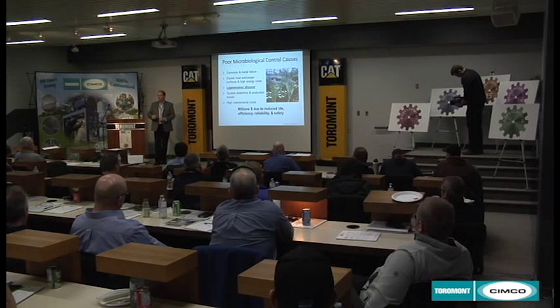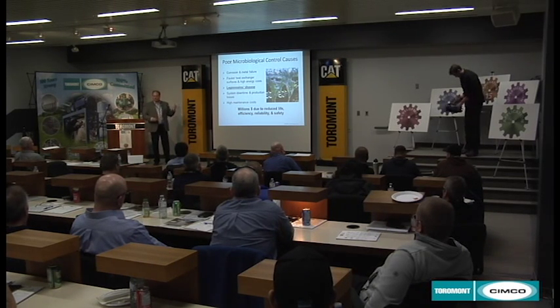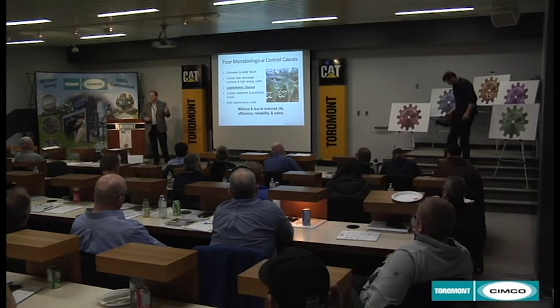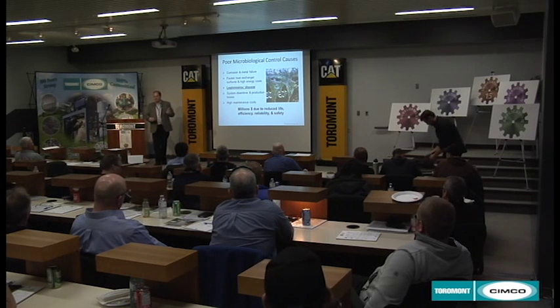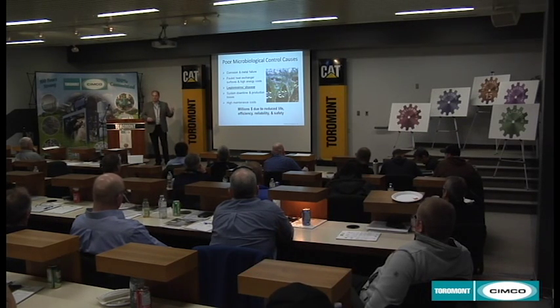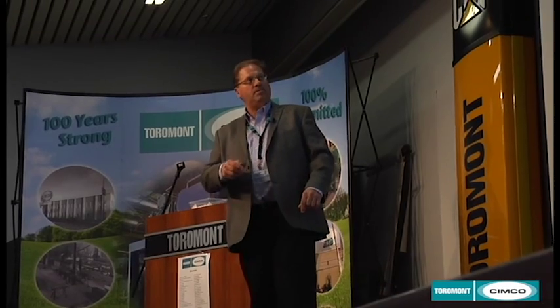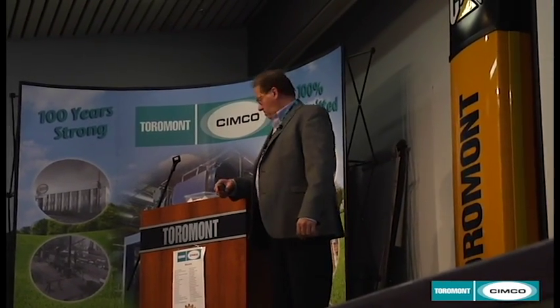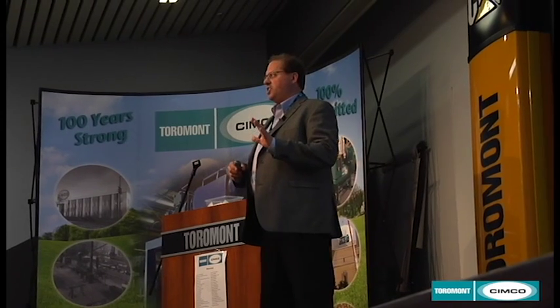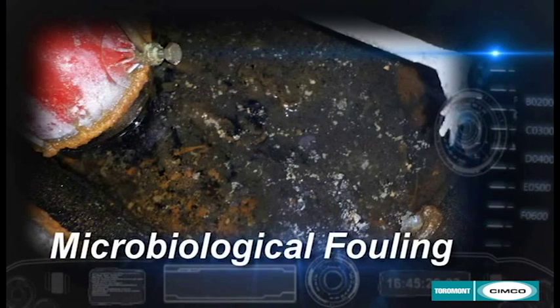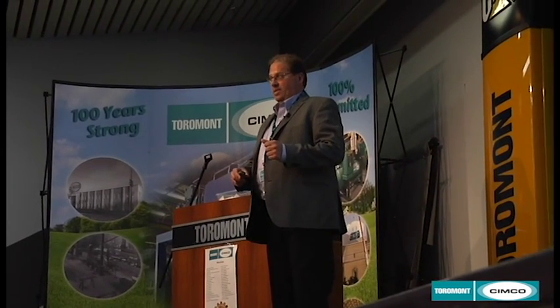Anybody have dogs? Do you ever wash the bowl that they drink out of? You'll feel a little slimy. That's fouling. That's microbiological fouling. That's a slime. And the thickness of that scale that we talked about in scale deposition, 1/32 of an inch, the energy consumption of a 7% increase in energy costs. If you look at the same thickness of fouling, that's a little severe, but same thickness of fouling in a condenser tube, you'll get 10 times the loss of energy on microbiological fouling than you have with scale deposition. So you're better off having scale deposition than microbiological fouling. If you see slime in your tower, you're going to have problems.